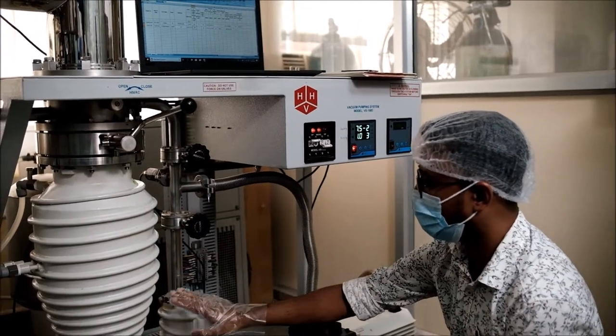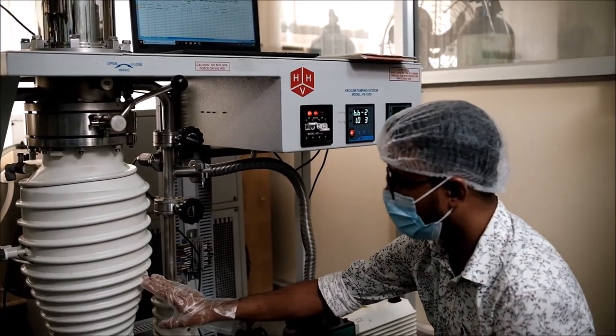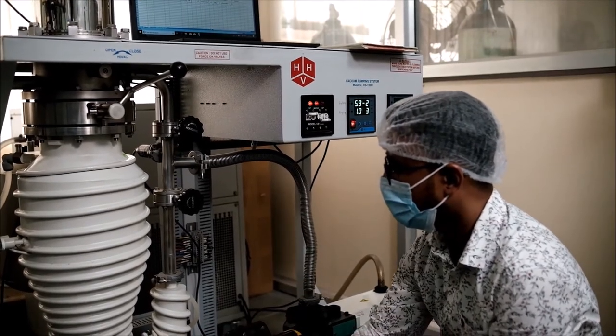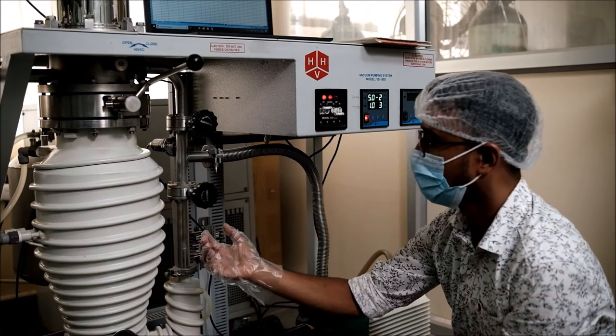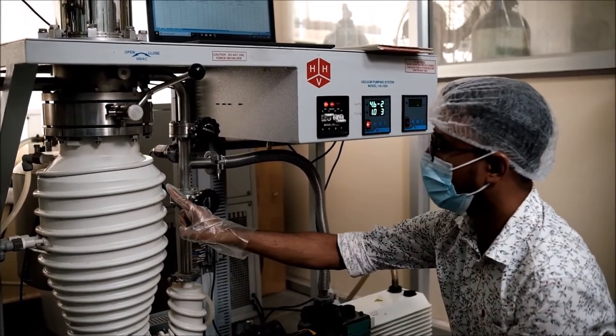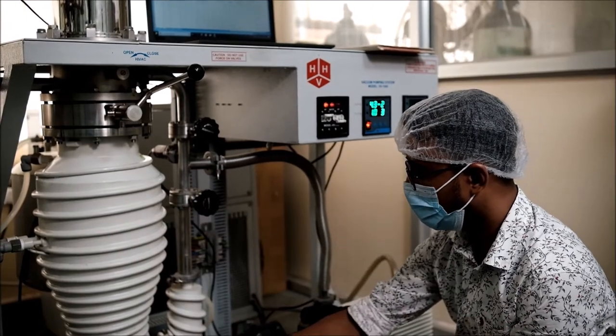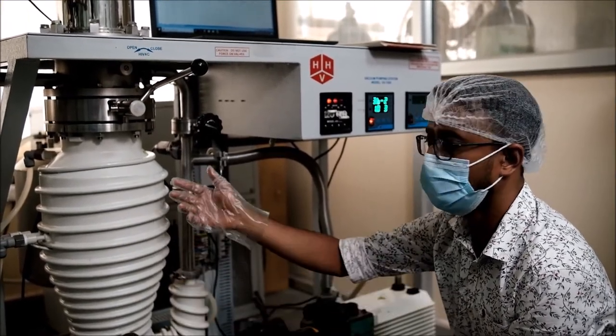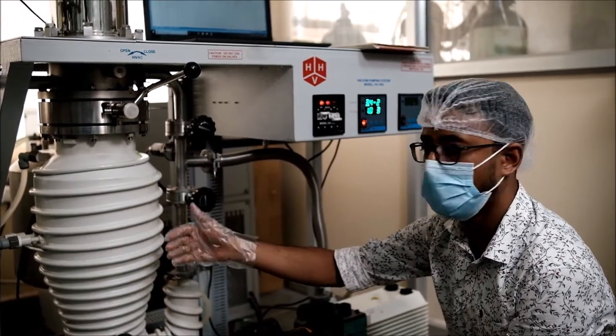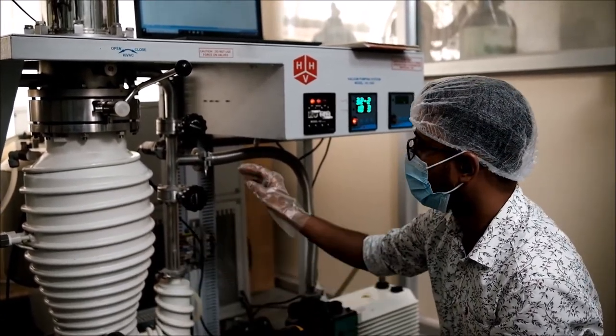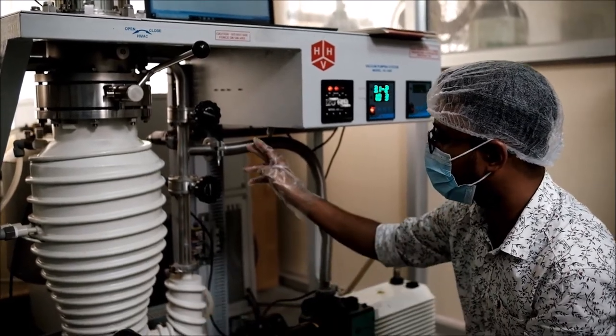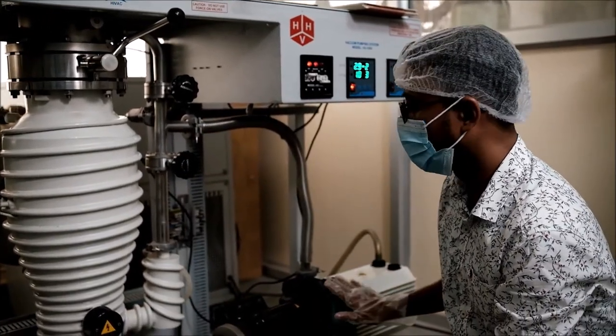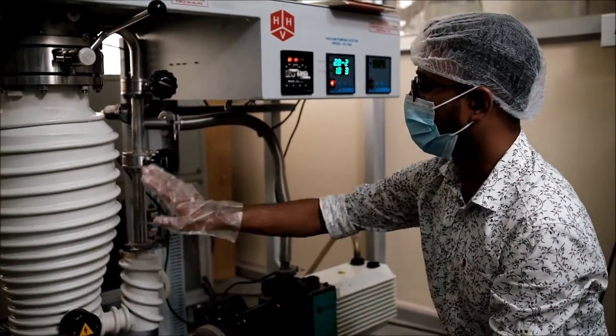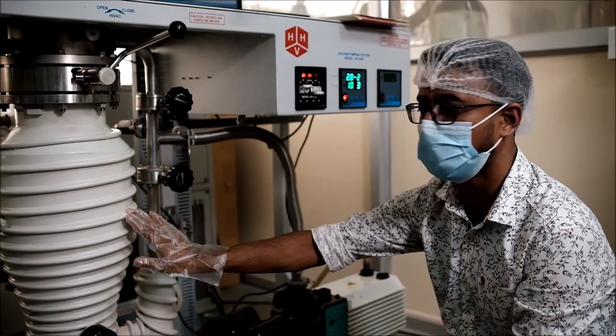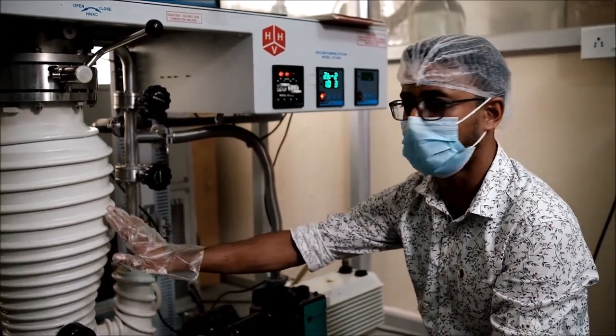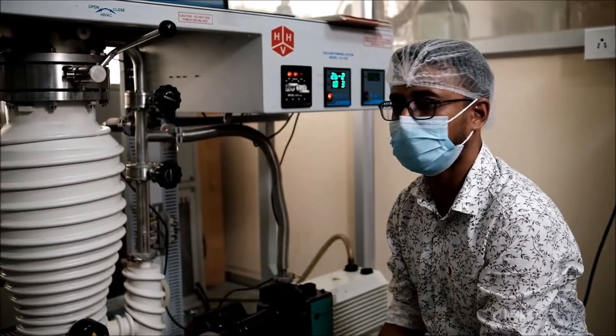This is very important for a diffusion pump because a diffusion pump works on the principle of jet creation from vaporized oil. So if we don't evacuate the diffusion pump chamber before heating up the oil, then the oil will burn with the atmospheric oxygen and this will destroy your diffusion pump's oil. So before turning on the diffusion pump, we have to evacuate the chamber, and this is done by this rotary pump. When the pressure reaches 10^-3 millibar, only then will we turn on the diffusion pump. So till then we will wait for a few minutes.